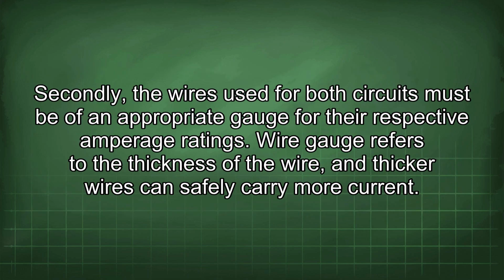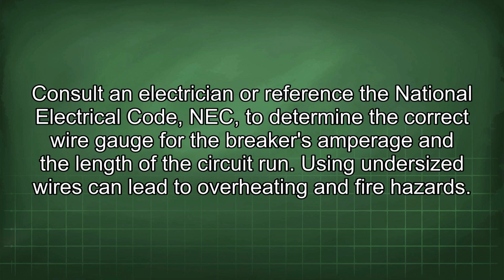Secondly, the wires used for both circuits must be of an appropriate gauge for their respective amperage ratings. Wire gauge refers to the thickness of the wire, and thicker wires can safely carry more current. Consult an electrician or reference the National Electrical Code (NEC) to determine the correct wire gauge for the breaker's amperage and the length of the circuit run. Using undersized wires can lead to overheating and fire hazards.